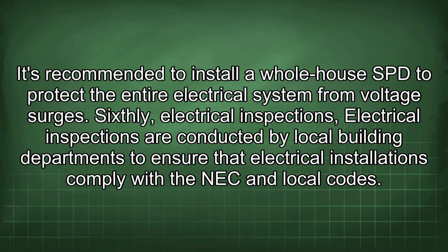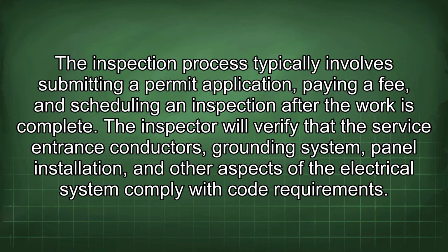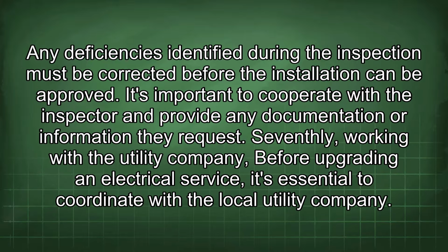Sixthly, electrical inspections. Electrical inspections are conducted by local building departments to ensure that electrical installations comply with the NEC and local codes. The inspection process typically involves submitting a permit application, paying a fee, and scheduling an inspection after the work is complete. The inspector will verify that the service entrance conductors, grounding system, panel installation, and other aspects of the electrical system comply with code requirements. Any deficiencies identified during the inspection must be corrected before the installation can be approved. It's important to cooperate with the inspector and provide any documentation or information they request.